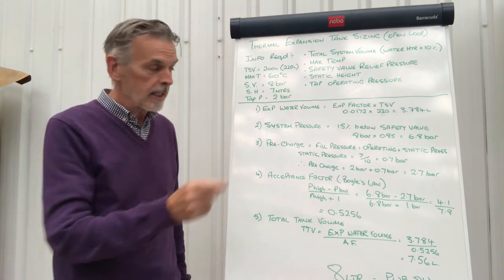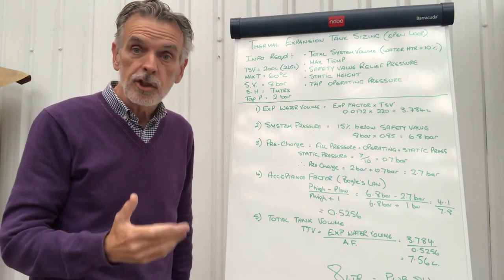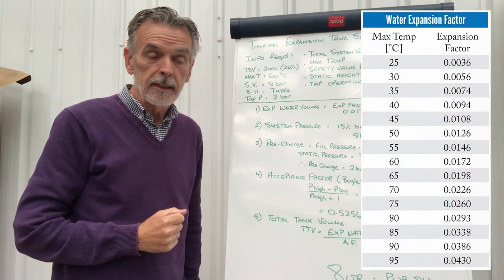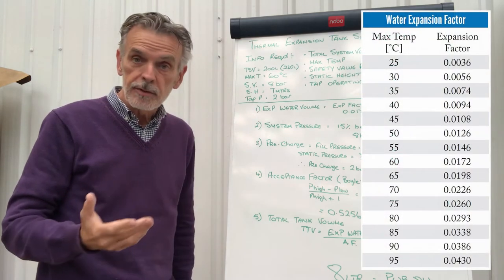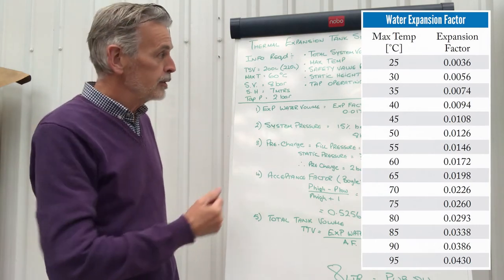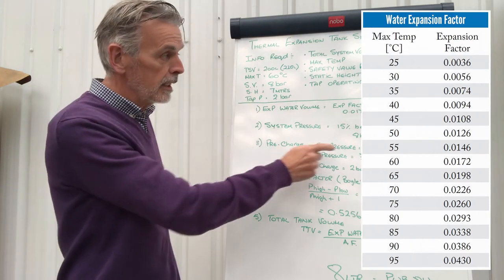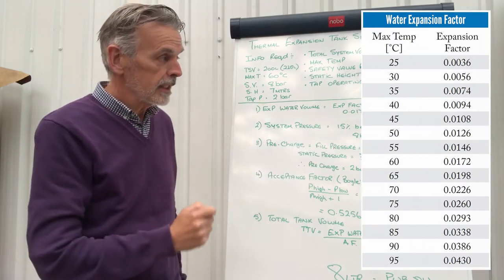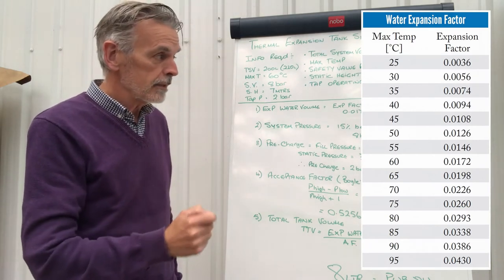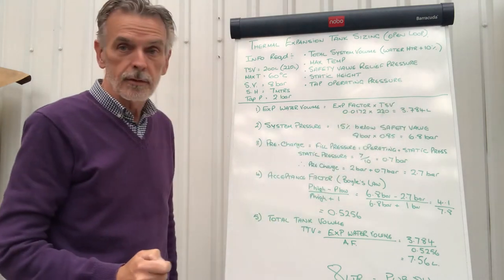First thing that we need to calculate is the expanded water volume, and that's basically a chart lookup table which is here on the screen, which I'll leave there for a few seconds while you look at it. But basically you look down the chart, you look at the temperature that you're storing the water at, which is now at 60 degrees, and you can see that the value is 0.0172. So 0.0172 times 220 litres is equal to 3.784 litres.